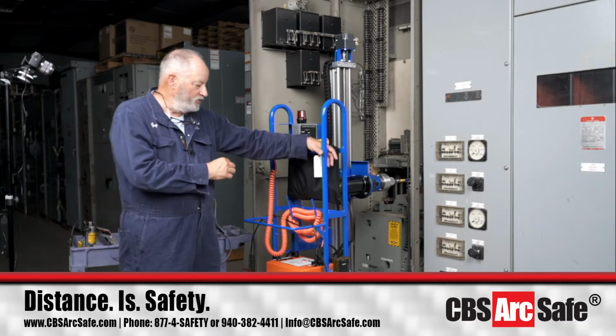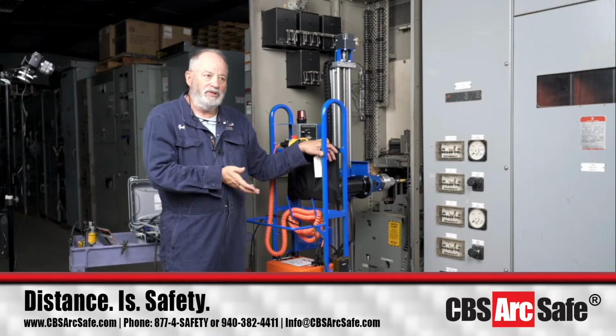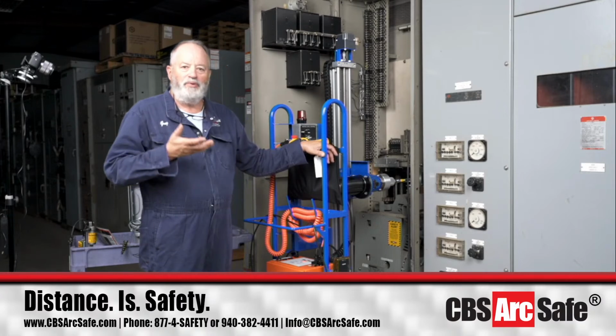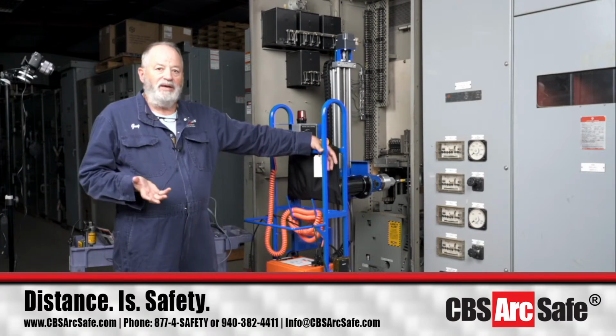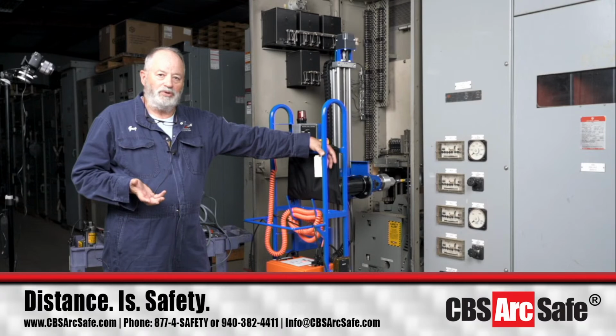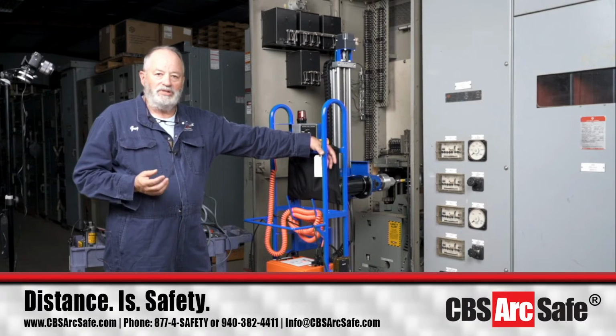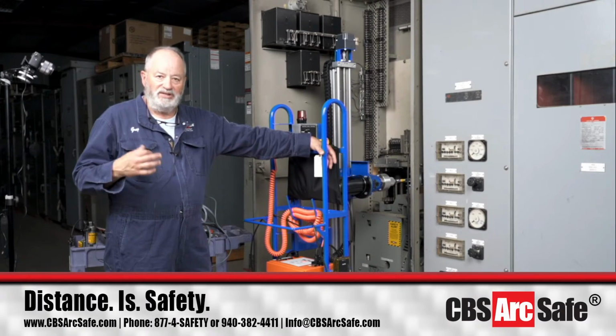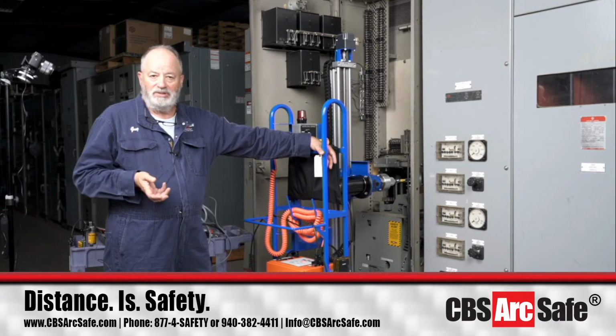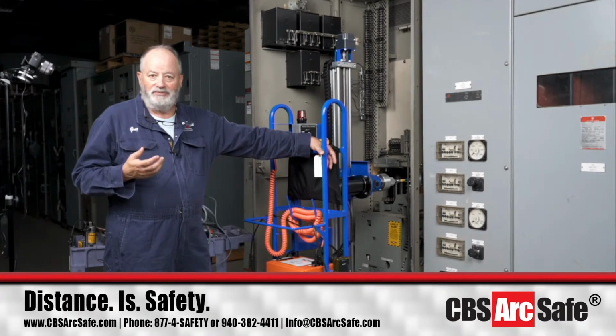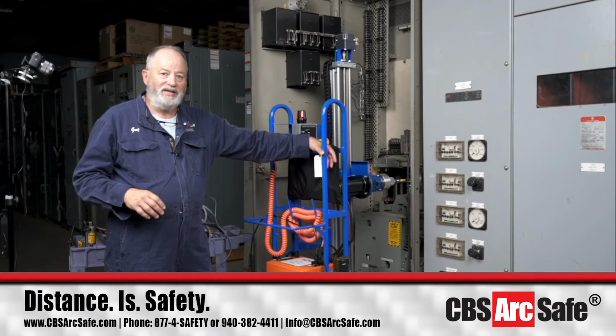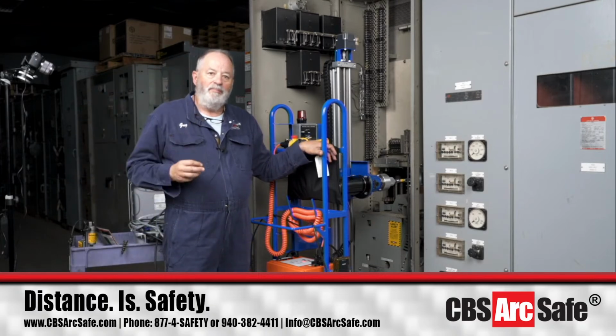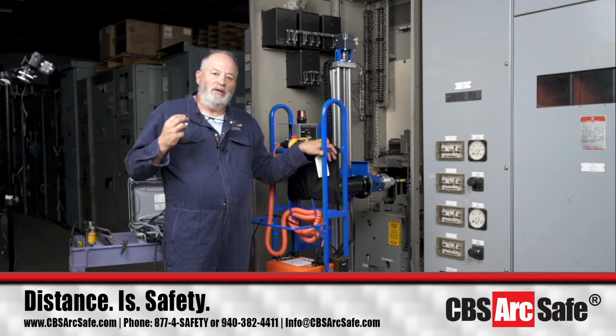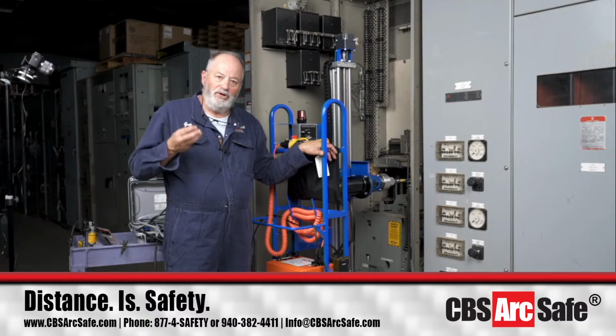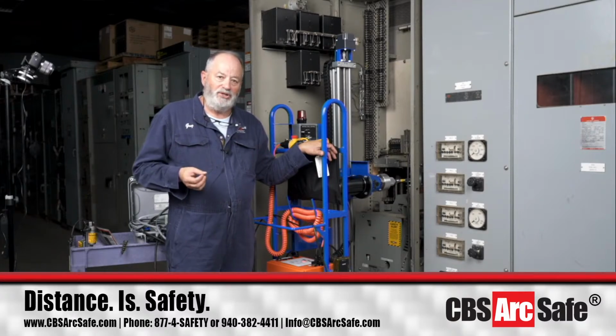For most of your Magne-Blast breakers, even though you're doing a lot of work raising these breakers, most of the time you're using less than 20 foot-pounds of force. So you'll see the CCM running for about 17 to install when you hit the bus, and about 12 to 14 for removing the breaker. And that can even be for the large ones, because the gearing in the cubicle gears down the amount of force required. It just takes longer.